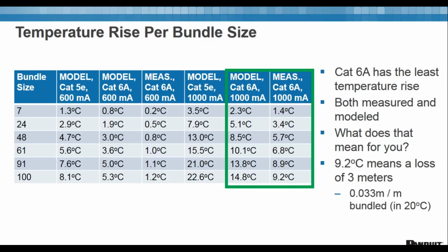So at around 600 milliamps, a Category 5E system is supposed to get up to about 8.1 C with a large bundle. The model says 6A is only about 5.3. What we've measured internally is only about 1.2. So there's a very negligible impact on lower power PoE for heat rise with a 6A system. Now when you go up to a higher 1,000 milliamp system, 5E is at about 22.6. The model says 6A should be about 14.8. What we've actually measured on a Panduit Matrix system is 9.2.